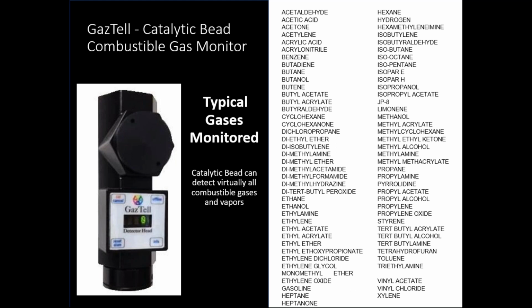And that holds true for all these chemicals that you see on this list. I think there's only one or two chemicals that I know of that have a higher ignition temperature than methane, and they aren't detected by this sensor. But it's not a common chemical, so you wouldn't necessarily see it out there.